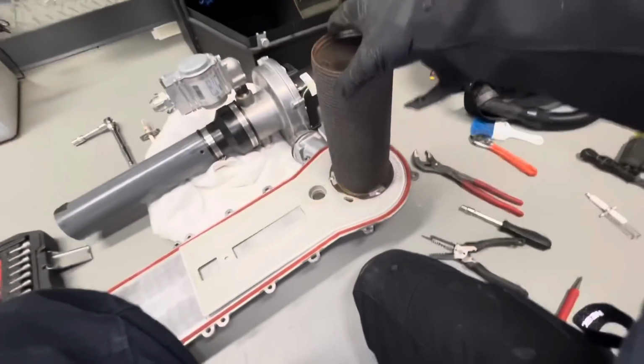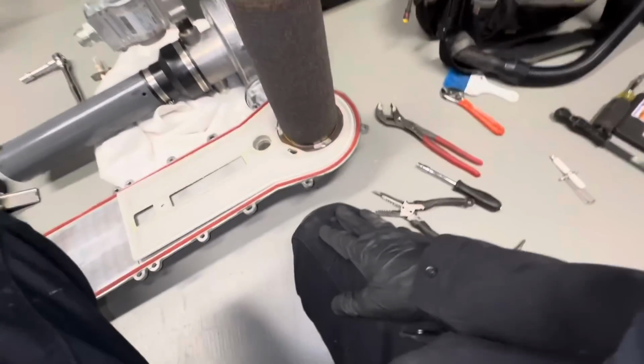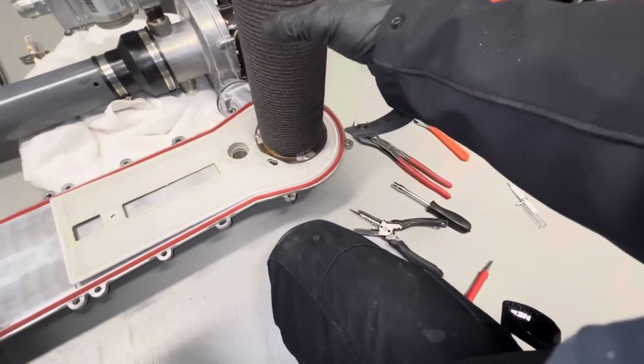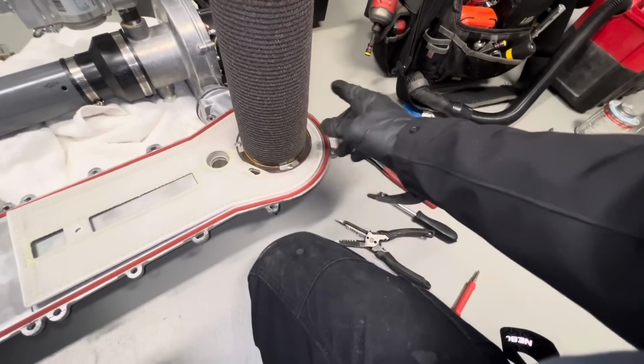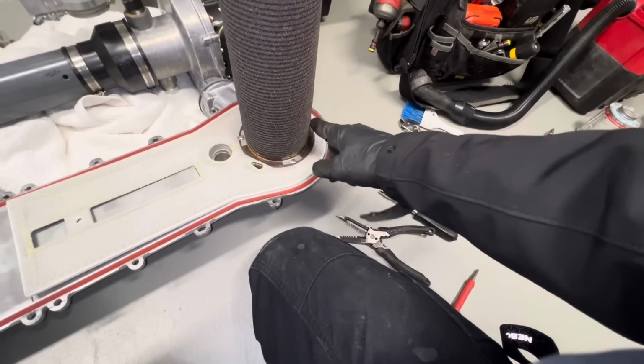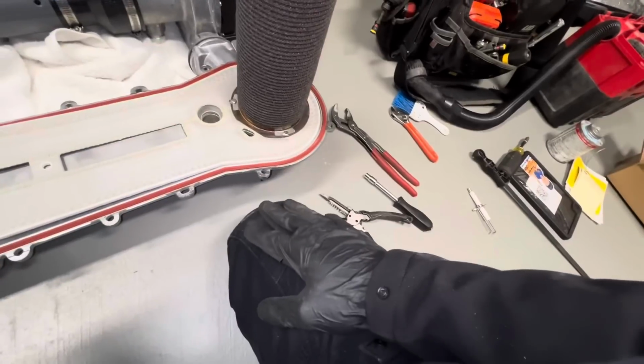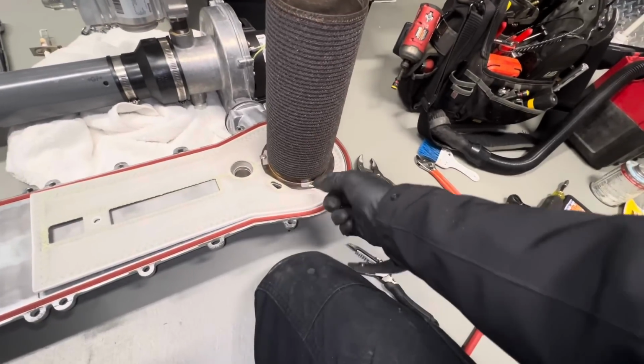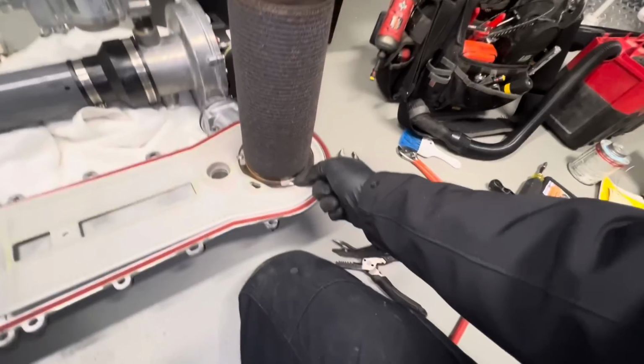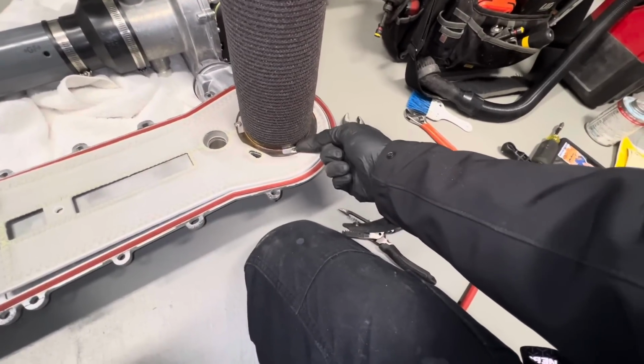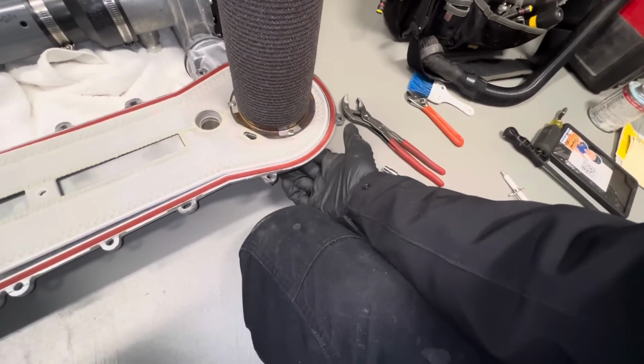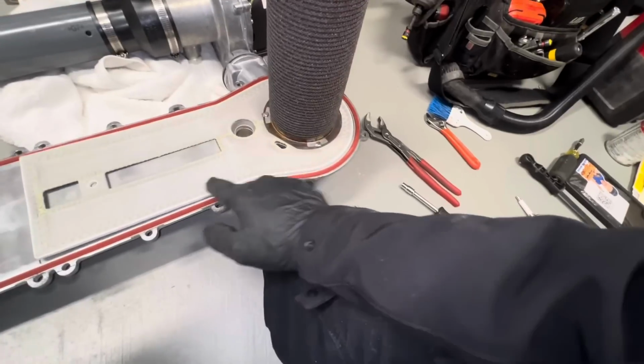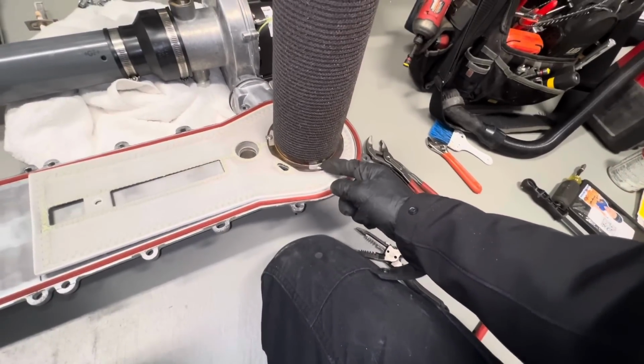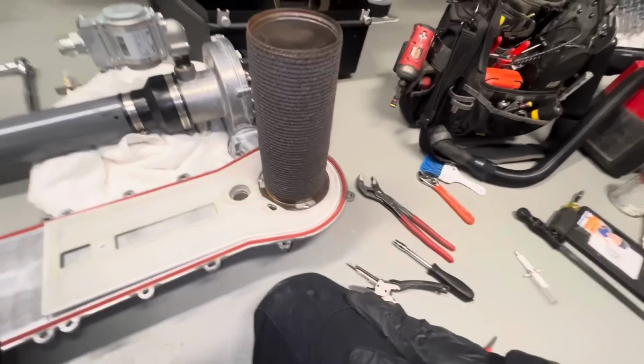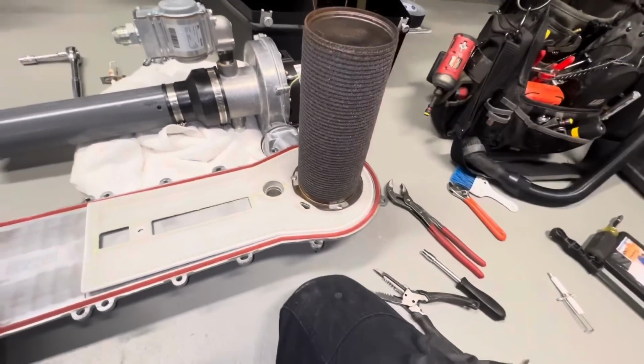And I see it a lot when people have done a maintenance and left that down, and the burner starts to sag or crumble, and then pull off, and then you get big leaks of air and gas coming out of here, and it booms. And I've seen it where it might have been a possibility that when the boom happened, it actually pulled the plug in the aluminum that holds the threads, so he ended up needing a new cover plate because we couldn't bolt on the burner to the unit when we got a new burner. And now we have a problem.